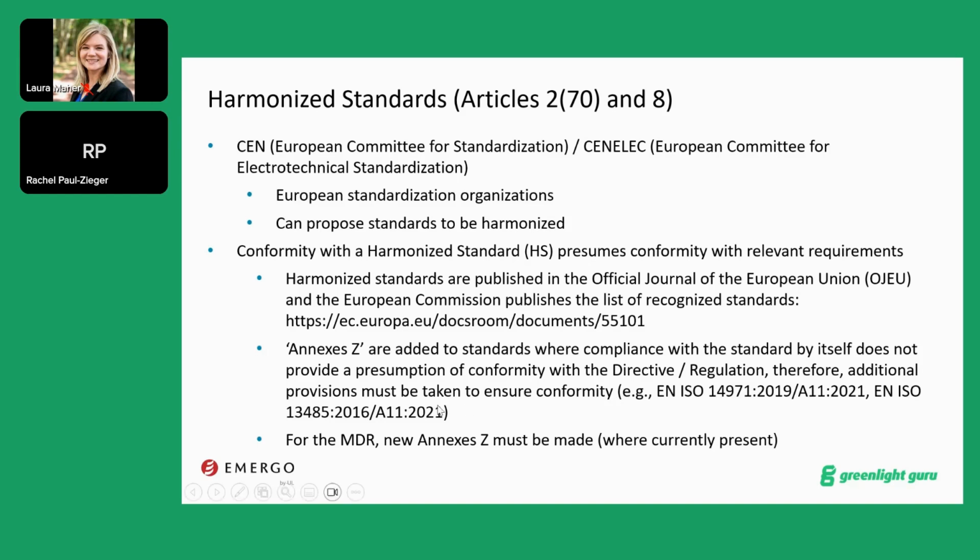And now you have also Annex Z. Annex Z is added to standards where compliance with the standard by itself does not provide a presumption of conformity with the directive and regulation. So in fact, Annex Z provides a kind of gap analysis between the standard and the regulation. And to be in full compliance with the regulation, you need to take into consideration this additional provision.